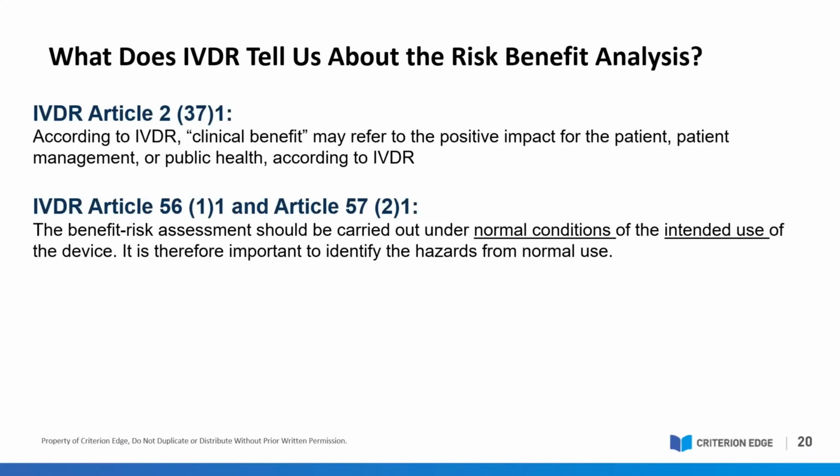For IVDR, unless a clinical benefit is presented in an intended purpose or in a product claim, the downstream clinical benefits are not taken into consideration in a benefit-risk analysis. However, downstream risks should be considered as part of the overall risk. So really the good news is that IVDR recognizes that the concept of clinical benefit for an IVD is fundamentally different from that which applies to a pharmaceutical or a therapeutic medical device.